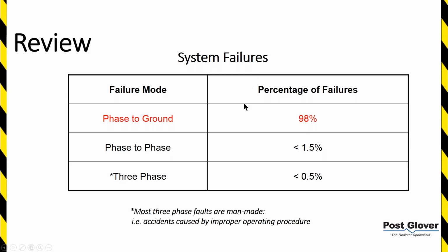So the reason why I bring this up is because, generally speaking, resistance ground benefits you when you have a phase to ground fault. It's very similar to a solid ground system in the other two failure events. So we could talk about incident energy, all this other stuff, but my bottom line is it's essentially the same otherwise, but the phase to ground fault is going to help you a lot.